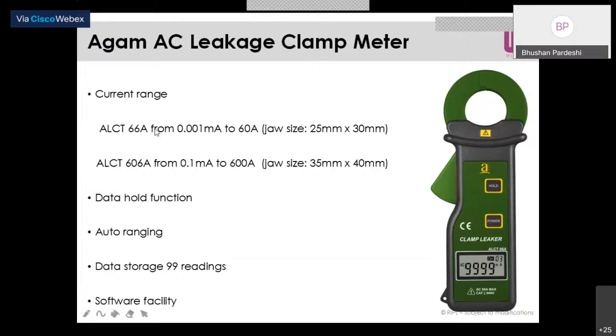This leakage clamp meter, the ALCT 66 ampere, allows one to measure the leakage current from 1 microampere to 60 ampere. Just imagine 1 microampere, how low a value it is. That low an AC leakage current one can measure in this device. As we all know, we use earth leakage relays or other devices for protecting the system from any leakages. But to identify the leakage at the site using a handheld device, this particular instrument will help one measure the leakage current available in the system, and depending on the current rating, the jaw size of the device changes.